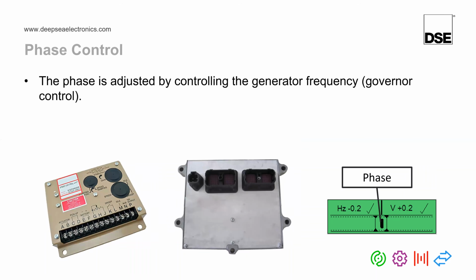And finally, for synchronizing, we need to worry about something called phase. Phase is measured in degrees of difference between one supply and another. So just because two supplies have the same voltage and frequency does not mean they are in sync. You also need to make sure they are at the same phase, effectively have both waveforms lying on top of each other. Now, the way in which we change the phase of a generator is we slightly increase its frequency. So for example, the generator you're synchronizing to might be at 50 Hertz, and the generator that is doing the synchronizing might be at 50.1 Hertz.